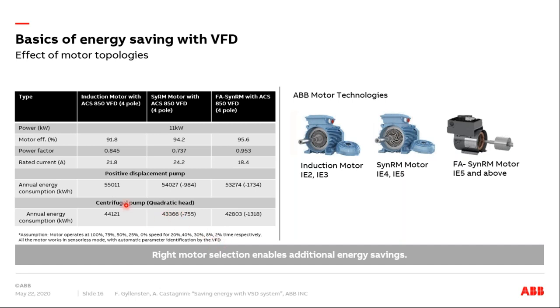I'm taking an example of an 11 kilowatt motor here, and you can see the relative efficiency of the motors. I'm using two different types of pumps here. One is the positive displacement pump to start with, and you can see that the total energy consumption per year decreases as you go to a high efficiency machine. How much energy and cost is saved will depend upon the cost of energy at that location.